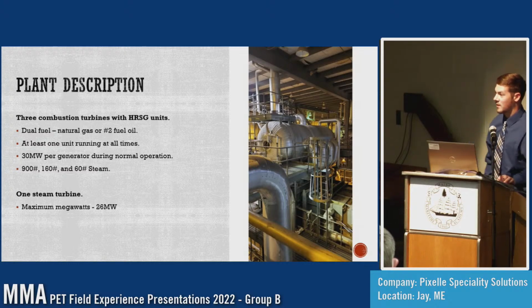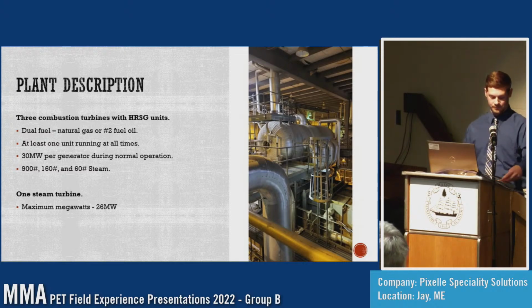Each HRSG produced 900-pound, 160-pound, and 60-pound steam. The 900-pound steam was 450,000 pounds per hour if all 3 units are running. The 160-pound steam was 120,000 pounds per hour, and the 60-pound was 50,000 pounds per hour.